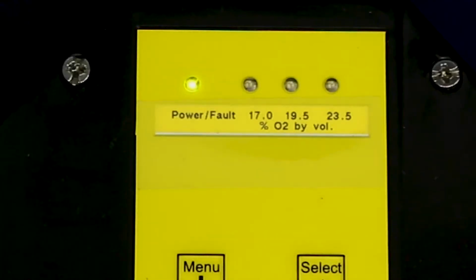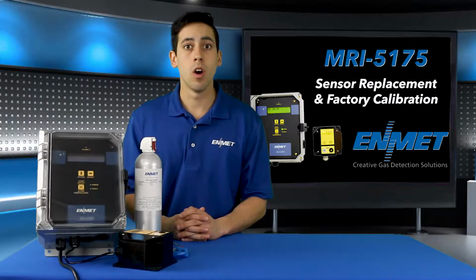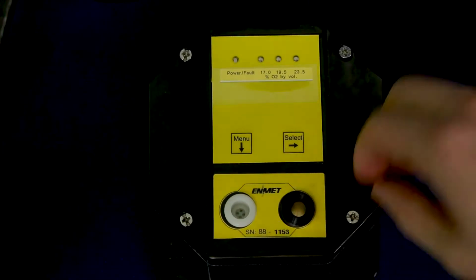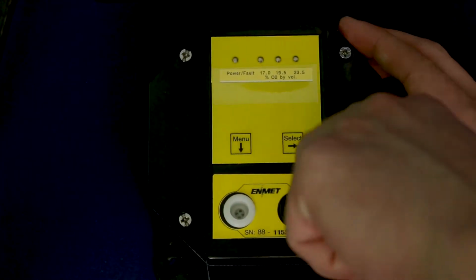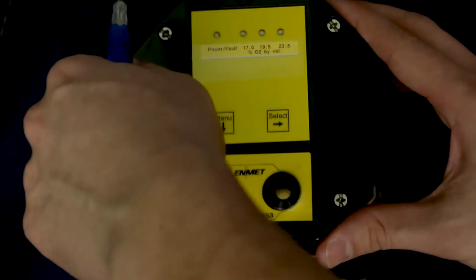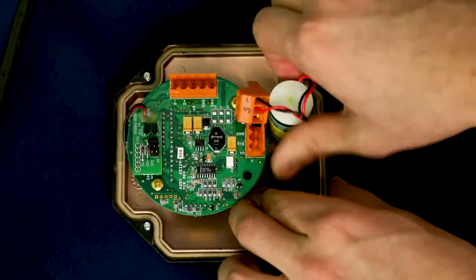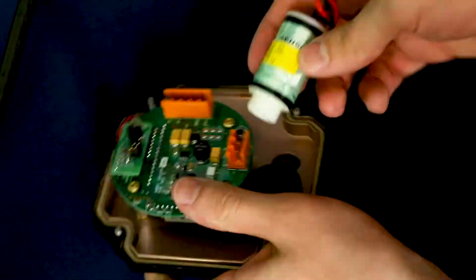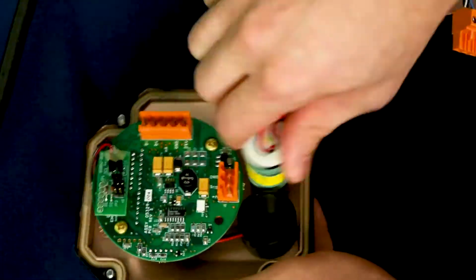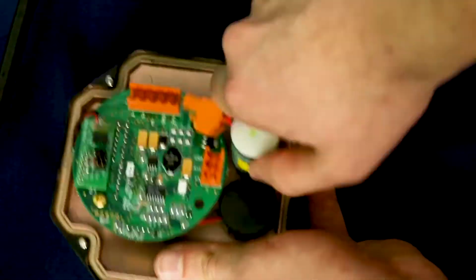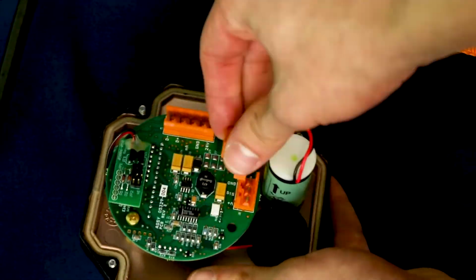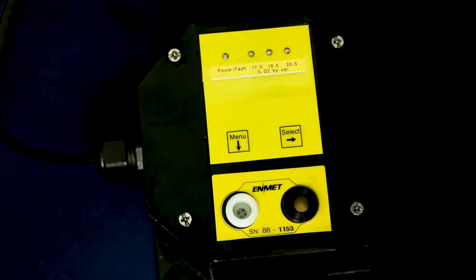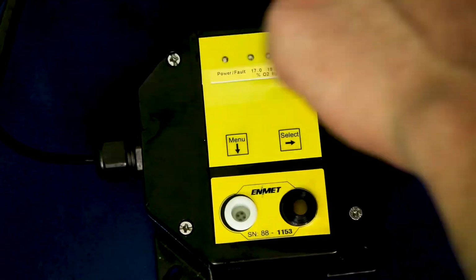Turn off the electrical power to your MRI unit. Once it is powered off, open the display panel and remove the 4 cover lid screws. Once the screws are removed, take off the lid to access the sensor and the instrument. Remove the old O2 sensor by unscrewing it and replace it with a new sensor. Once you've installed the new sensor, put the cover lid back on and screw it into place.